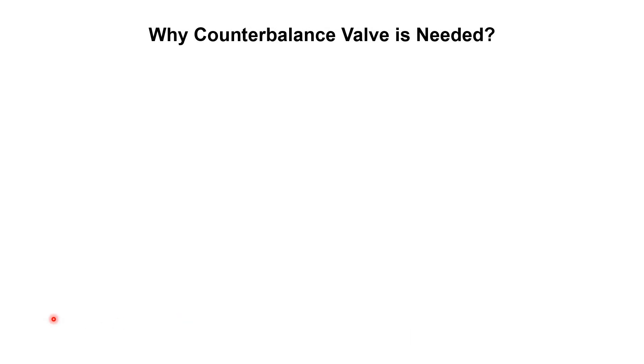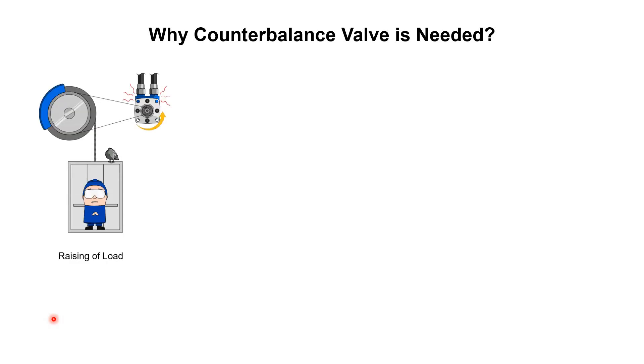To understand the counterbalance valve, a question arises: why is a counterbalance valve needed? To answer this question, we will consider this diagram. Here a hydraulic motor is used to drive a sheave, and then this sheave is used to raise an elevator. This hydraulic motor provides drive to the sheave, which is used to raise and lower the elevator. When we are raising this load, it will be a normal operation.